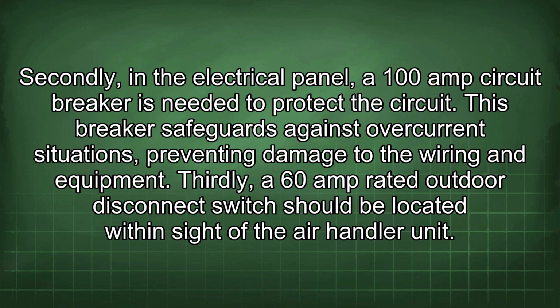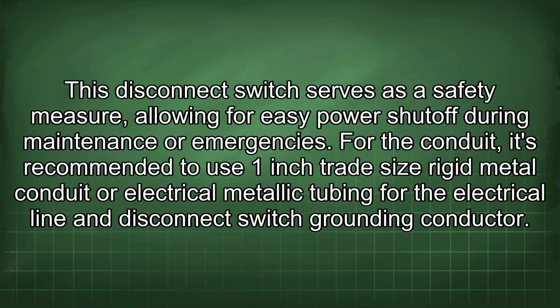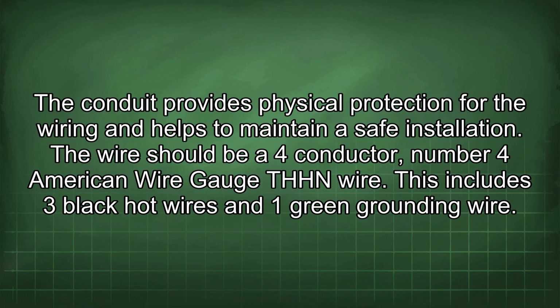Thirdly, a 60 amp rated outdoor disconnect switch should be located within sight of the air handler unit. This disconnect switch serves as a safety measure, allowing for easy power shutoff during maintenance or emergencies. For the conduit, it's recommended to use 1-inch trade-size rigid metal conduit or electrical metallic tubing for the electrical line and disconnect switch grounding conductor. The conduit provides physical protection for the wiring and helps to maintain a safe installation.